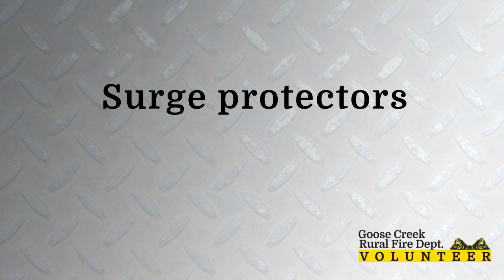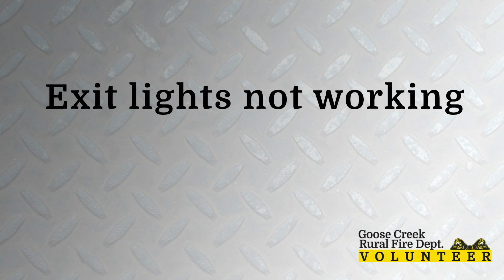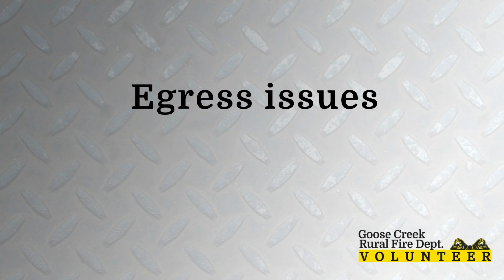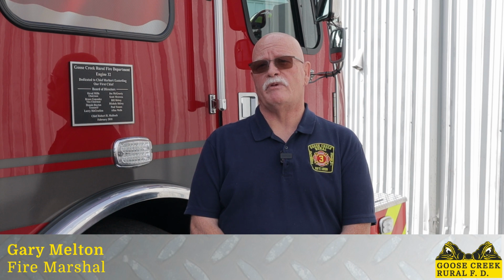Surge protectors being extensively used and overpowering electrical circuits, receptacles without plate covers, extension cords being used as permanent wiring, exit lighting that's not functioning properly, emergency lighting that's not functioning properly, usually due to dead batteries because they're not getting checked regularly. Egress issues. Egress is the clear path from the business to the public right of way, and these need to be maintained clear.